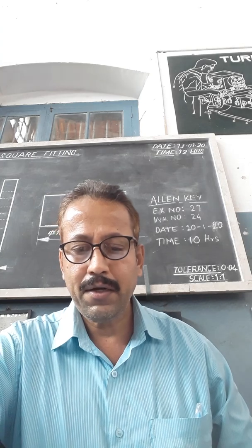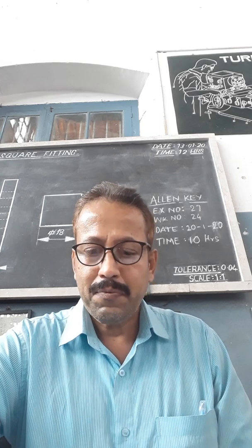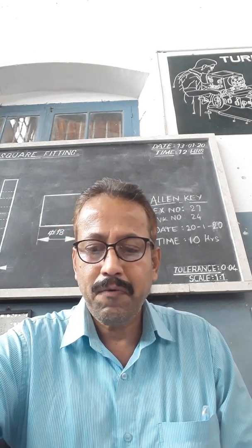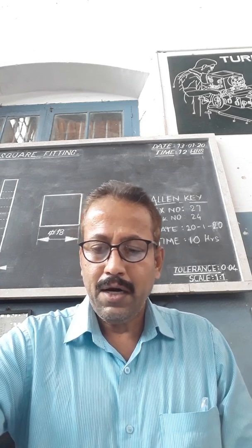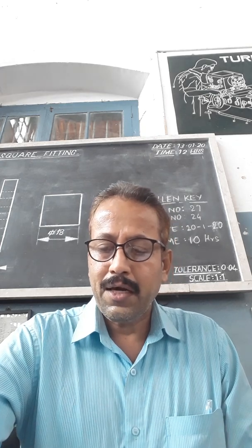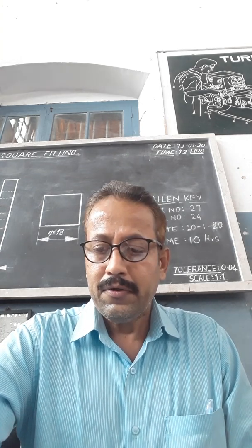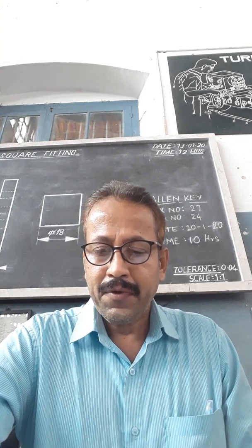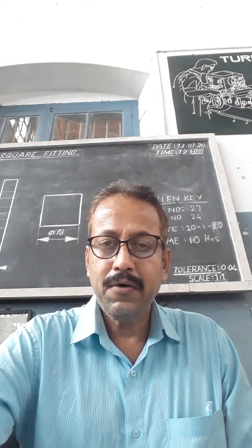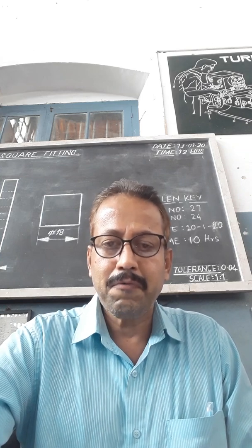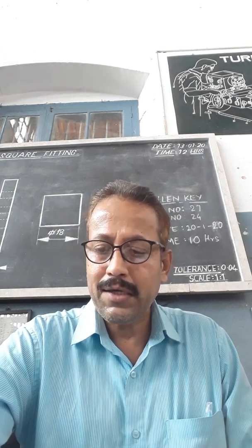So the example is given here: 44.8725 with the help of a 112 piece set. As per the calculation, when this size 44.8725 is given, after the decimal point there are 4 divisions. So try to cancel the last division, that is the last digit, 5. By selecting the first gauge in that 112 piece set, 1.0005 piece is there. So when you subtract this piece from 44.8725, the answer is 43.872. That means the last division is cancelled.